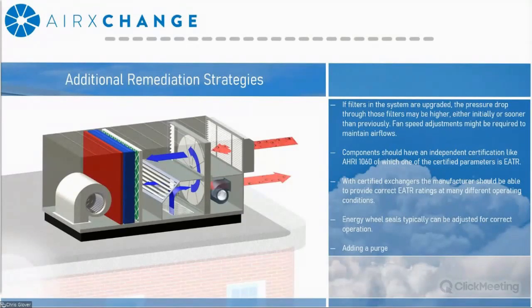And lastly, not all systems are equipped with a purge, as I mentioned before, and once again, to be honest, not all systems are required to have one. Adding a purge may be done to an existing system, but once again, it's going to change the system dynamics quite substantially. So you're going to want to check with the unit manufacturer or an HVAC engineer before just adding one into a system to really determine if it can be done or if it's even required in this case.